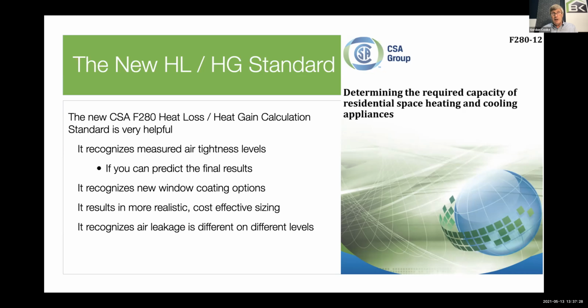So it doesn't take into account how a brick house heats up because it assumes the brick is vented. So I said they're conservative, and in this case, actually, they're not conservative. Where it would come in is if you had ducts in the attic, you would be asked to show the duct losses. So you would put in a calculation for the duct losses due to ducts being in the attic space. So that is a piece that you can put into a heat gain calculation in F280, but it does not increase the temperature of the attic in the summertime.